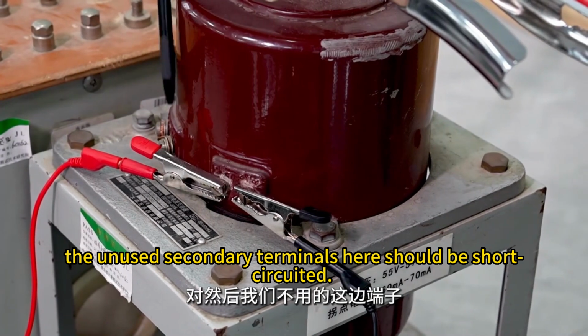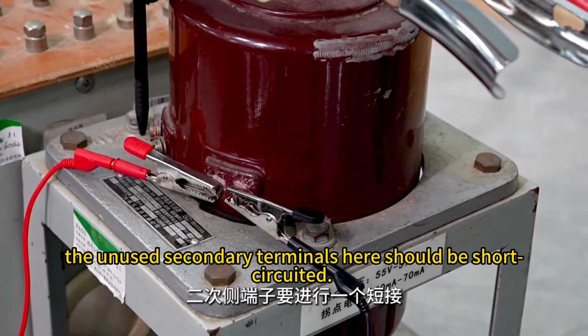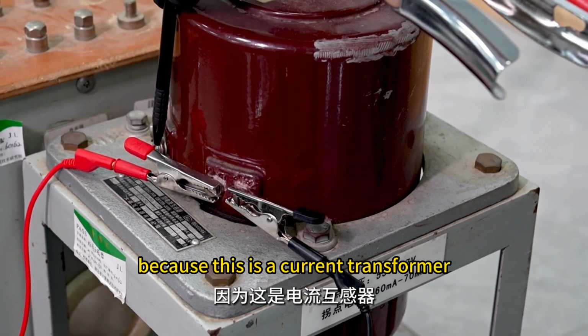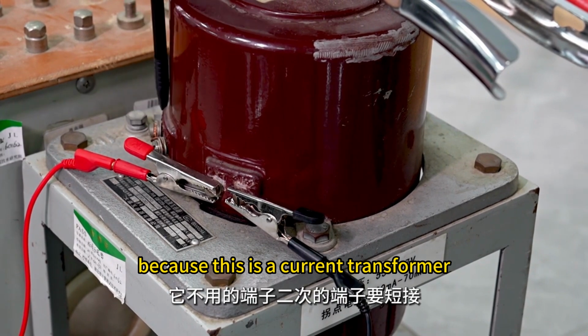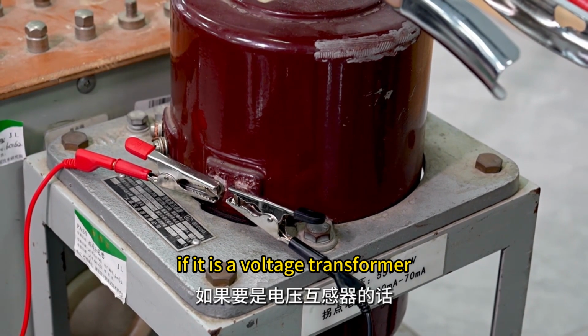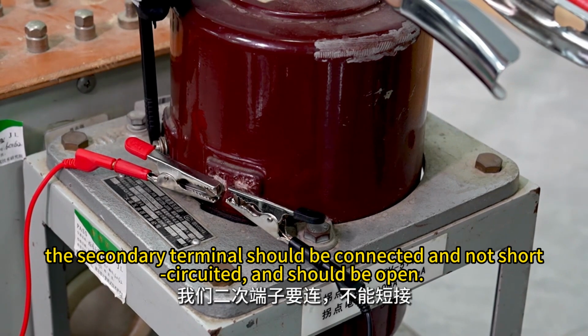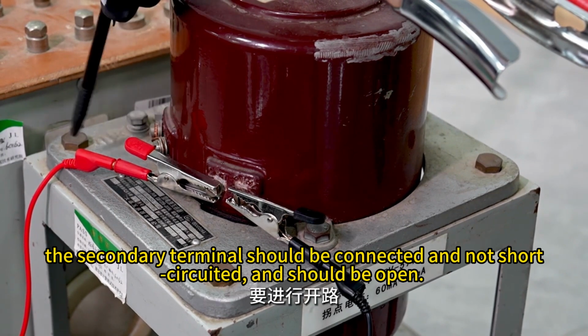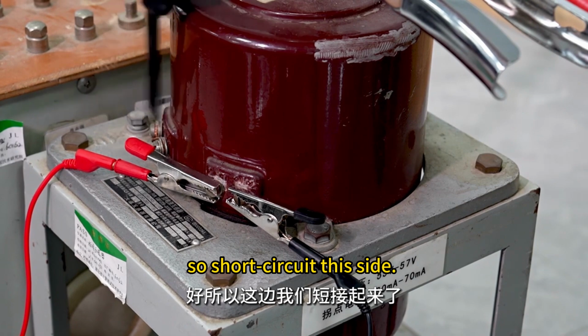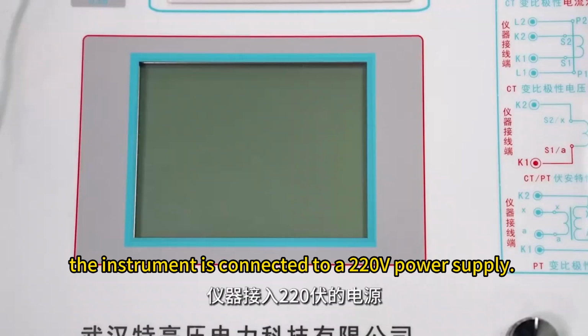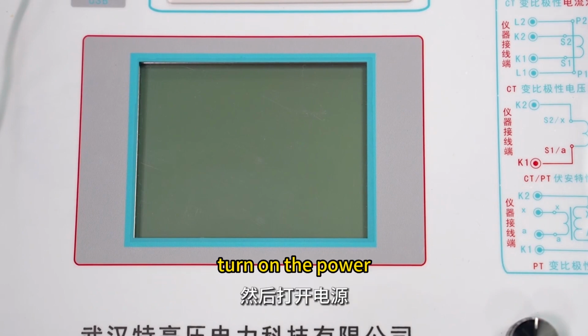The unused secondary terminals here should be short-circuited, because this is a current transformer. If it is a voltage transformer, the secondary terminals should not be short-circuited, and should be open. So short-circuit this side. The entire wiring is connected. The instrument is connected to a 220 volts power supply. Turn on the power.